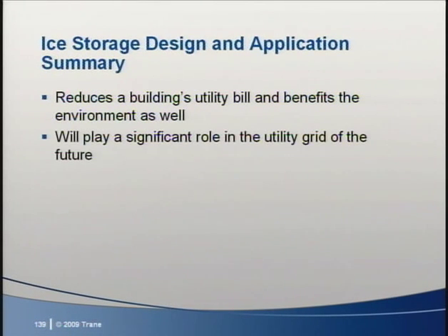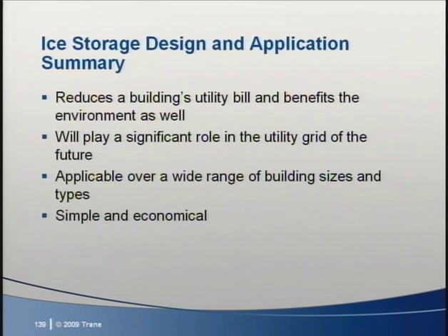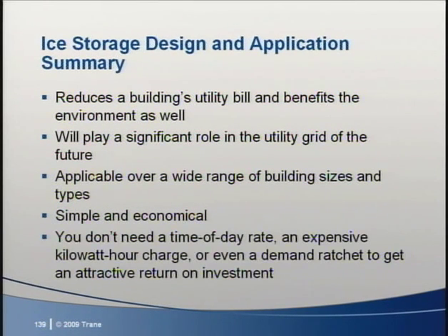Energy storage will play a significant role in the utility grid of the future. And ice energy storage is applicable over a wide range of building sizes and types. Adding ice storage to a chilled water system is simple and economical. And finally, for us, the biggest aha was that you don't need a time of day rate, an expensive kilowatt-hour charge, or even a demand ratchet to get an attractive 30% return on investment.